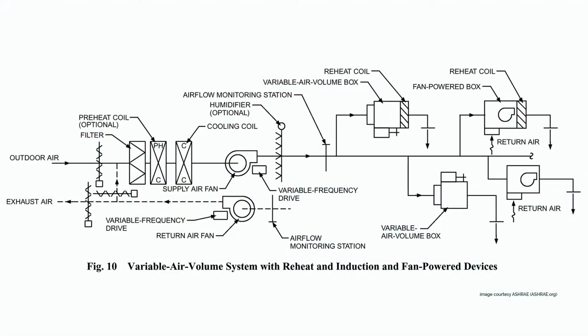It's important that you confirm your outside air dampers, sensors, and economizer mode logic are functioning properly and your systems are balanced as intended. We also recommend that you add a pre- and post-occupancy purge mode, where you simply operate the system with normal ventilation for at least a few hours before and after occupancy. Depending on the capabilities of your BAS, it may also be possible to implement logic to automatically reset and optimize ventilation rates in response to changing outdoor air conditions within the capacities of your equipment.